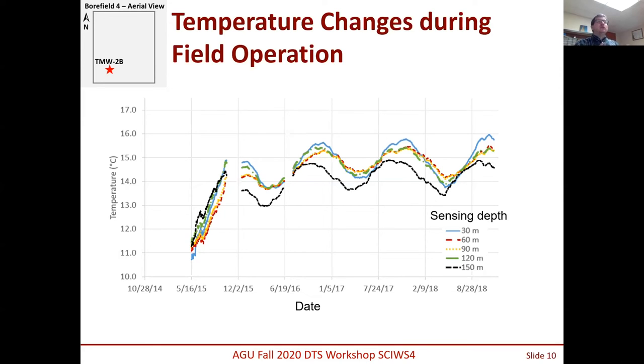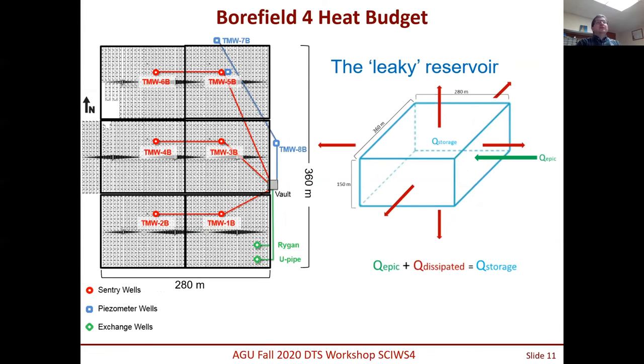They started to regulate the temperature increase. When they put the new borehole field into operation, they began resting the other fields to bring them to more balanced temperature conditions. Epic's system is cooling-dominated because of their computer power and large workforce — they only use it for heating about two months per year, even in cold Wisconsin. One objective of the project is to improve the engineering use of these fields by evaluating how the system behaves like a leaky reservoir — not only as a radiator but also as heat storage — measuring how much heat Epic adds or removes and monitoring storage temperature across the field.